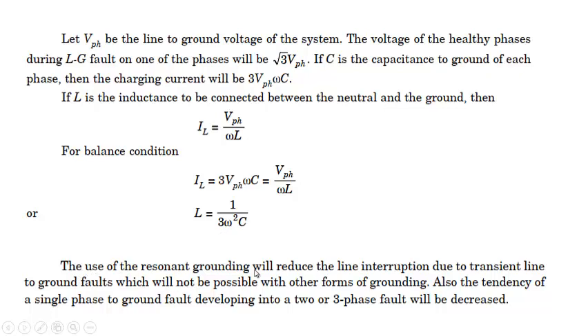The use of resonant grounding will reduce the line interruption due to transient line to ground faults, which will not be possible with other forms of grounding, because in this case the two currents exactly cancel each other. Also, the tendency of the single phase to ground fault developing into a 2 or 3 phase fault will be decreased. So this is the advantage of this.